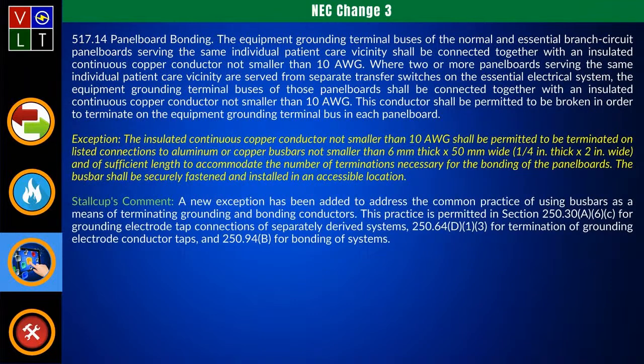They added an exception in 517.14, dealing with panel board bonding. This was added to address a common practice where they take and use bus bars as a means for terminating the grounding and bonding conductors.